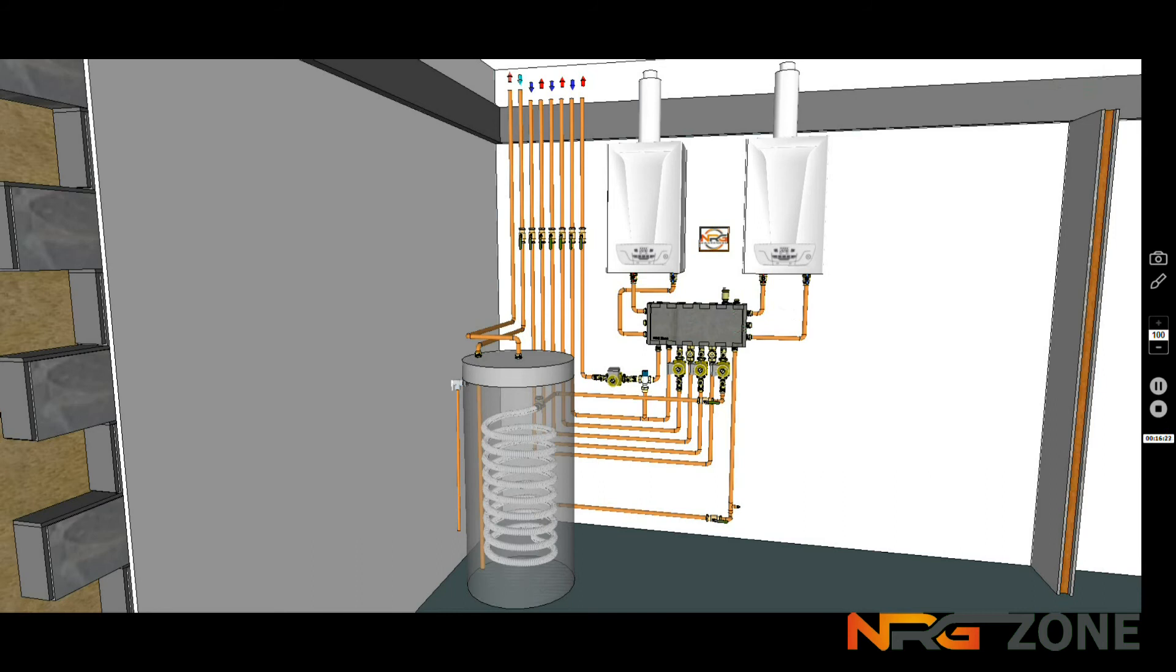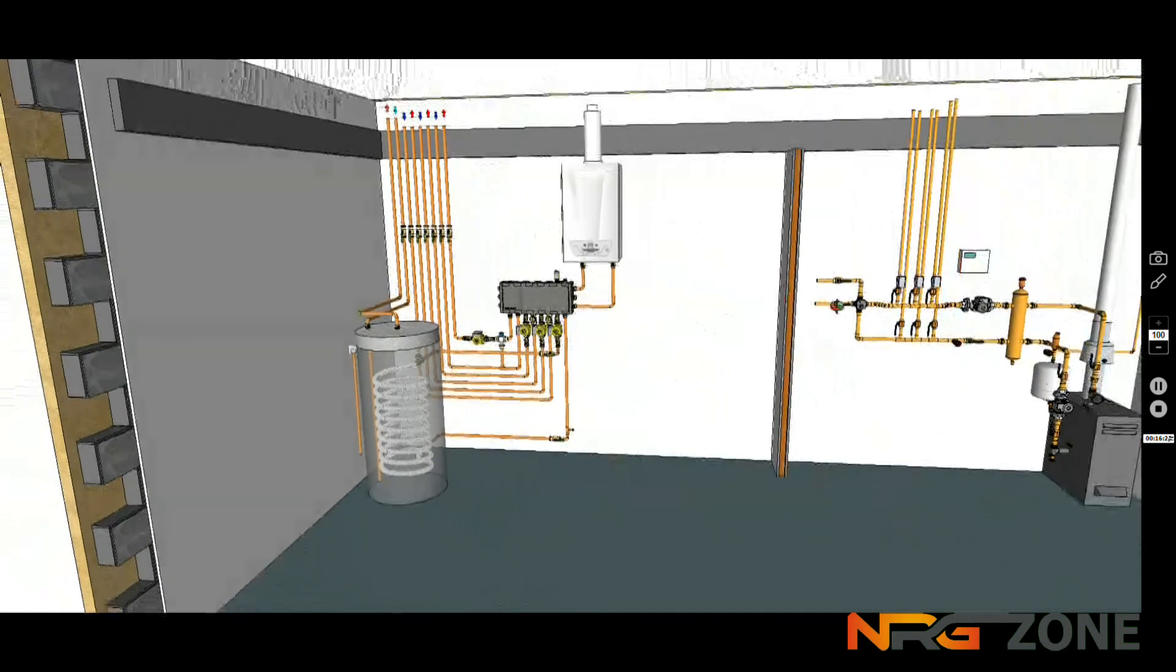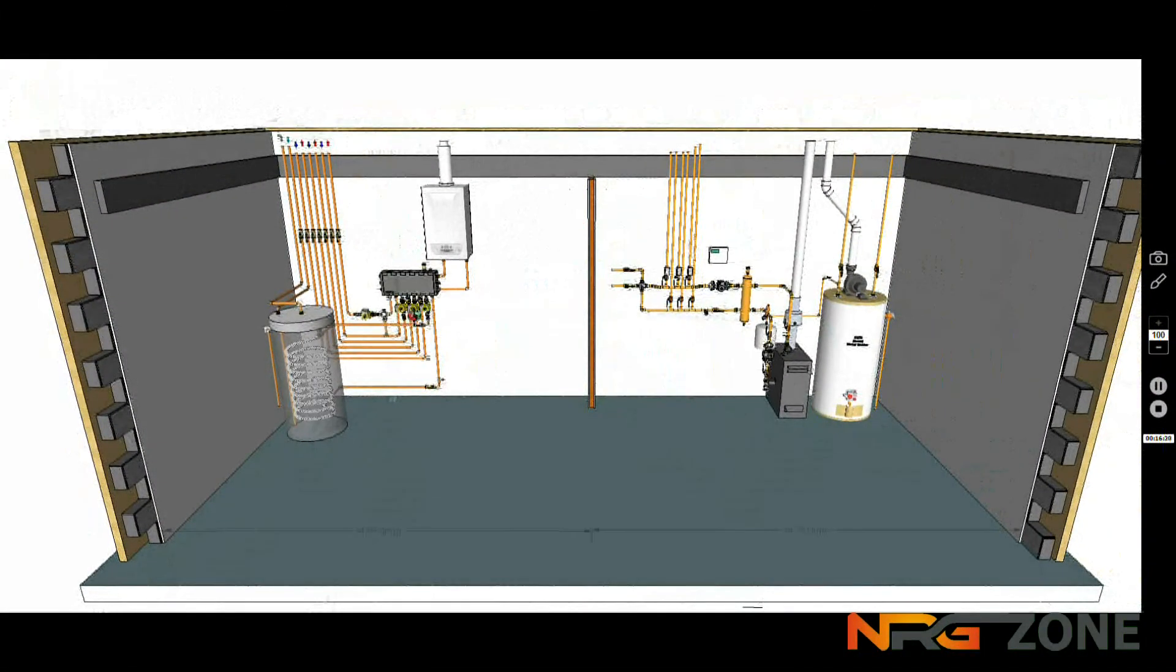If you look at what we have, it's a difference between the old and the new. The difference between having to put in all of these bits and pieces put together and the conflict of having to try to get the coldest water back to the boiler, which is impossible because the low loss header will be mixing hot with it continually. Also the fact that if you have a minor amount of central heating needed and some hot water, you have to fire two boilers to satisfy both of those conditions. Whereas in this situation you have one boiler that can modulate down to whatever amount of energy you're actually drawing off based on the hot water demand and the central heating demand. If hot water is needed it goes to full temperature, heats the water, and when hot water is not needed it goes back down to satisfy the exact heating requirements for whatever is necessary around the building. So completely more efficient way of going about the system.